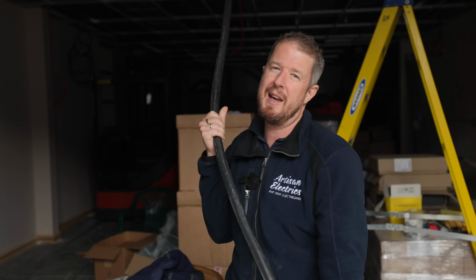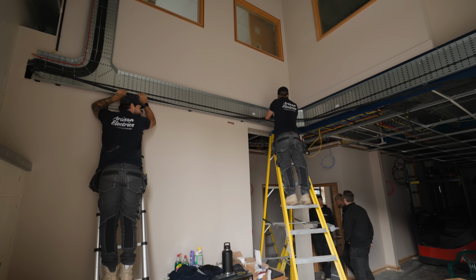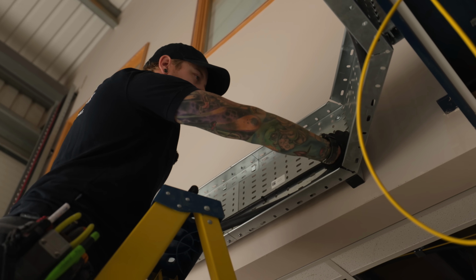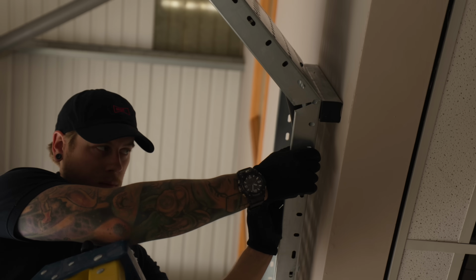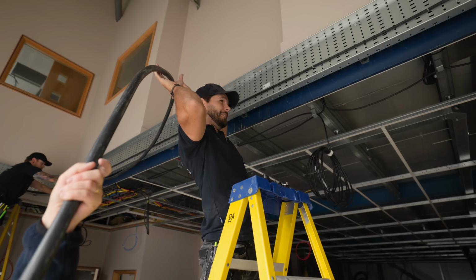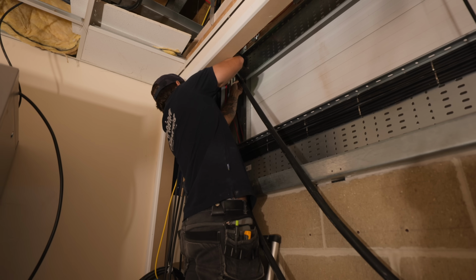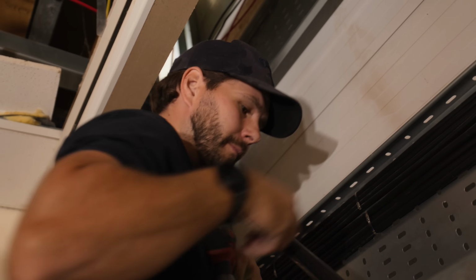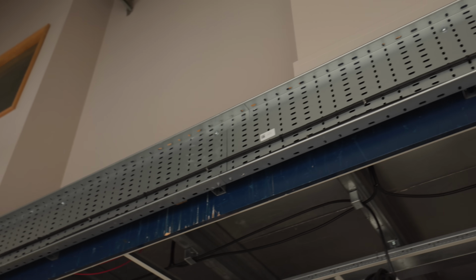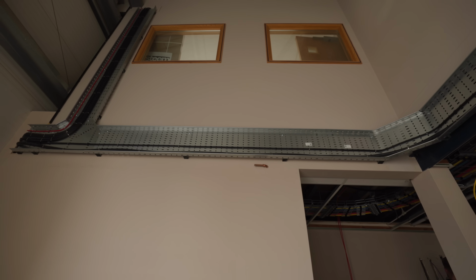With the volt drop calculations, we decided to go with 35 because it's about 50 meters of cable to get from the board to the inverter and back. The one downside to 35mm cable is it's quite tough to work with. So we've got one of those armoured cables in and the other one is about to go in. Tomorrow we're going to start mounting the batteries, so I'll see you in the morning.